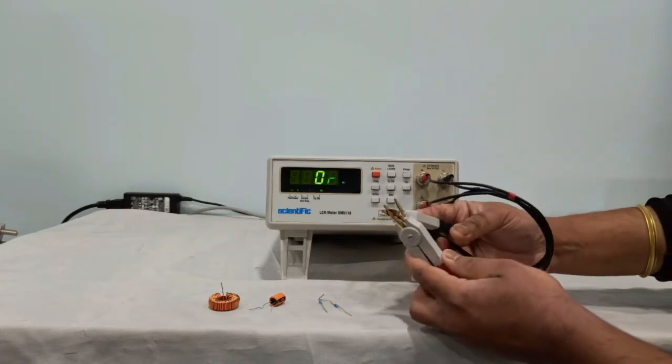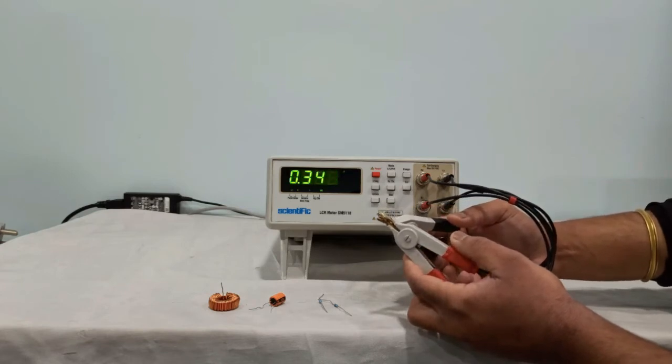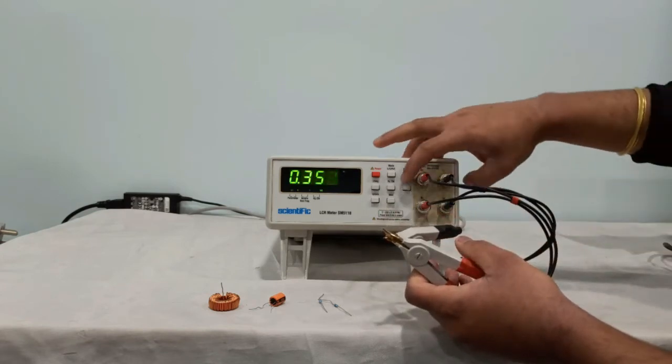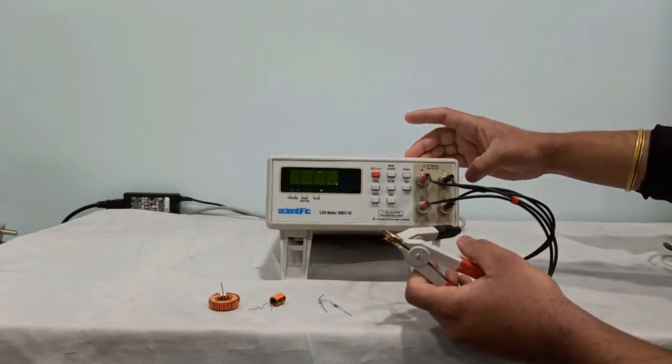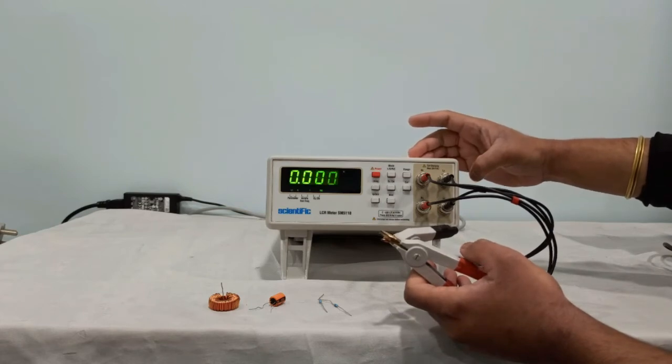If you want short compensation, short these two terminals and press CAL. This is how short compensation is done.